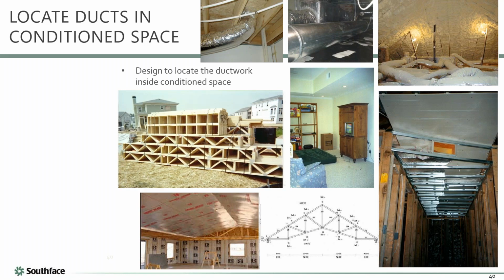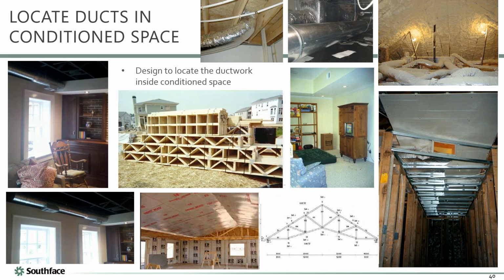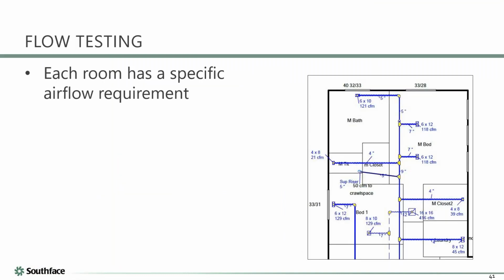If you're really good and you really pay attention to it, you have to really coordinate with the subs. It is possible to run ductwork between the first and second floor, and you blow the supply air up for the second floor and down for the first floor. You just really have to coordinate and design and make sure that the plumber doesn't run their pipe, you know, where they're not supposed to. And then my friends finished out their basement. They used exposed ductwork, so that's another option. So there are lots of ways to get the ducts inside. Please try to avail yourself of one of those design options.